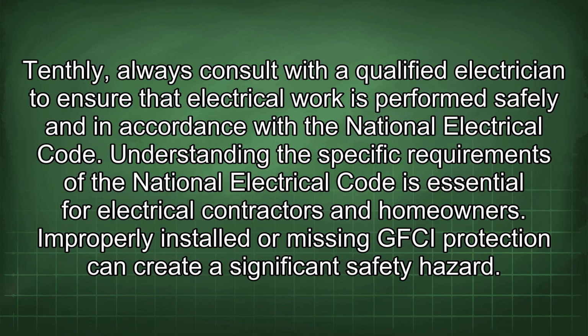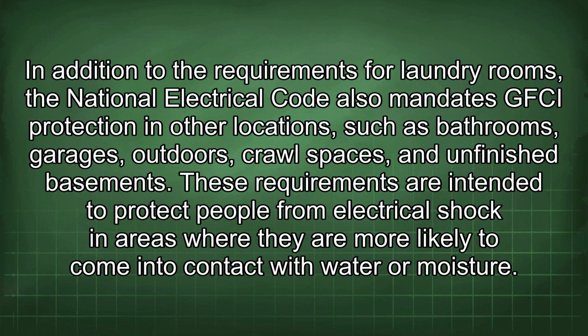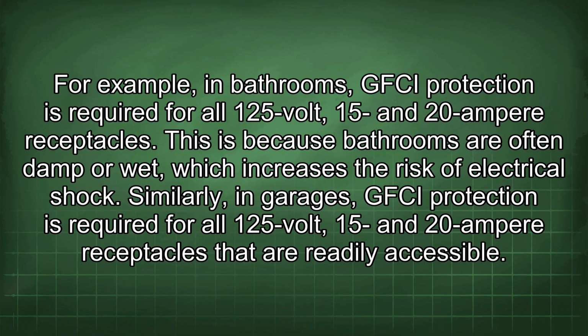Understanding the specific requirements of the National Electrical Code is essential for electrical contractors and homeowners. An improperly installed or missing GFCI protection can create a significant safety hazard. In addition to the requirements for laundry rooms, the National Electrical Code also mandates GFCI protection in other locations, such as bathrooms, garages, outdoors, crawl spaces, and unfinished basements. These requirements are intended to protect people from electrical shock in areas where they are more likely to come into contact with water or moisture. For example, in bathrooms, GFCI protection is required for all 125-volt, 15 and 20 ampere receptacles. This is because bathrooms are often damp or wet, which increases the risk of electrical shock.